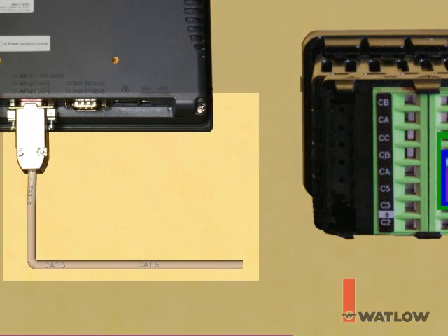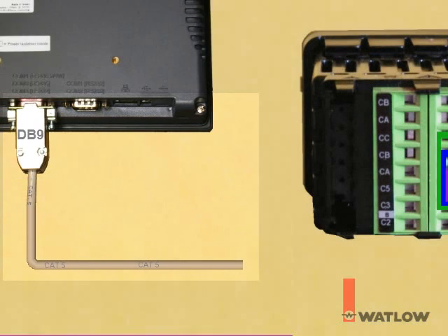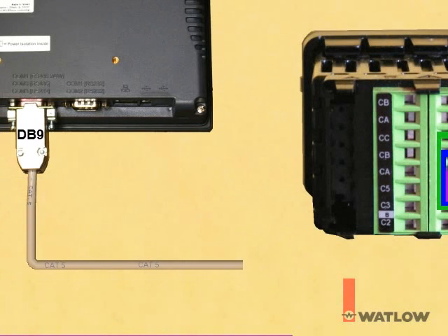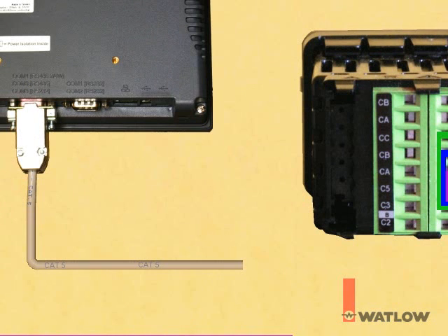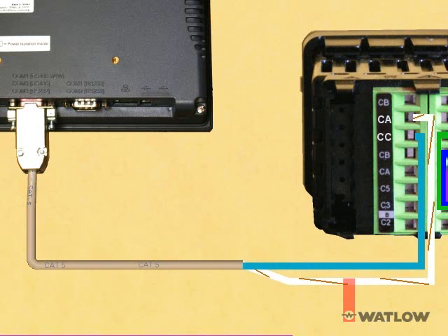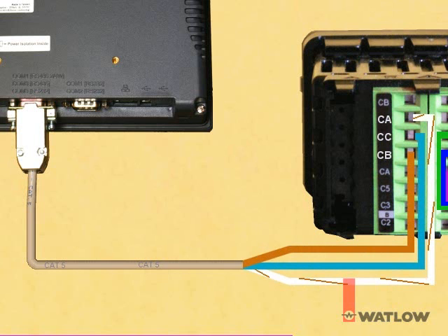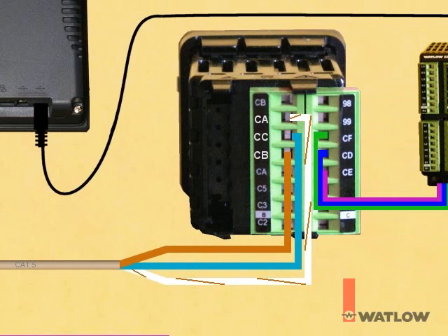The OIT is connected to the RUI gateway using the 485 cable available from Watlow. The DB9 connector goes into the COM1-485 connection on the OIT. At the RUI end, the white with brown stripe wire connects to CA, the blue wire to CC, and the brown wire to CB. The OIT is also connected to the laptop computer with a USB programming cable.